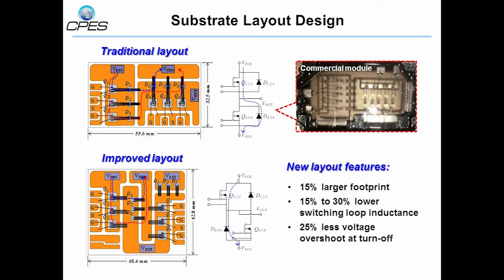Because of this rearrangement, the substrate pattern will be more complicated, which results in 15% larger footprint if following the same design criteria. But the new design is still able to achieve 15-30% lower inductances, and accordingly, 25% lower voltage overshoot at turn-off.